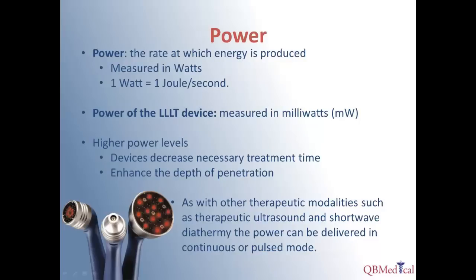The next parameter we need to be concerned with is power of the device. Power is the rate at which energy is emitted from the applicator, measured in milliwatts in low-level laser therapy devices. A higher power level will require a lower treatment time, as well as contributing to a deeper depth of penetration. As with other modalities such as ultrasound, we have the option to change the duty cycle, so we can apply a higher power in a pulsed mode.